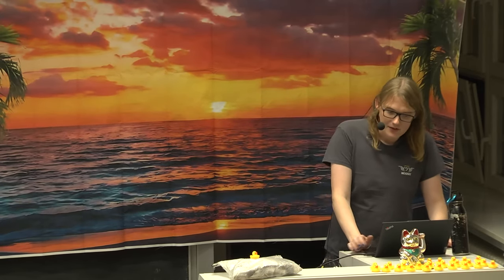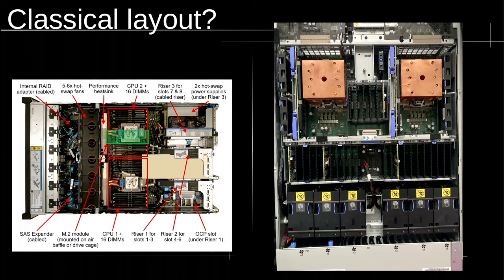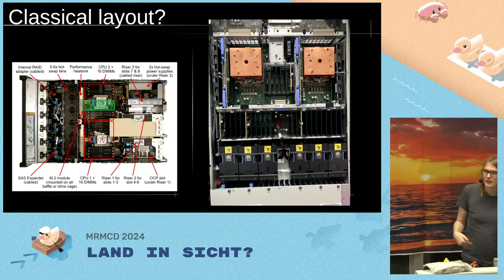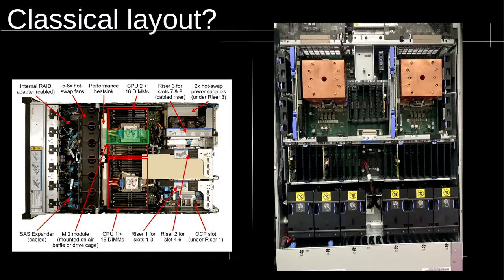Some manufacturers have been creative. For example, the IBM Power 10 system moves the memory all the way to the front of the chassis, so air first passes through the memory to cool it, then flows to the CPU blocks. Since memory DIMMs have no heat sinks, the airflow needs to be cooler and move faster over them.